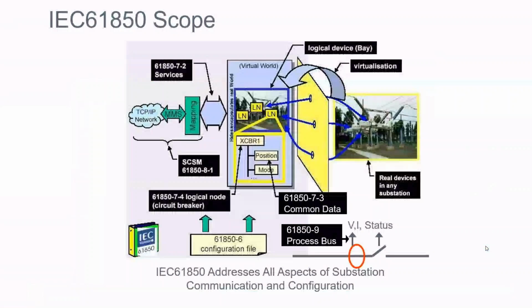61850 is the Ethernet-based protocol. What 61850 attempts to do is virtually model things within our substation. In this example, I'm showing modeling of a breaker. A breaker is what we call a logical node within the substation, and we can model it, creating all the aspects and attributes we need, like the circuit breaker's position, the controls, any metering, any CTs that might be part of that breaker.